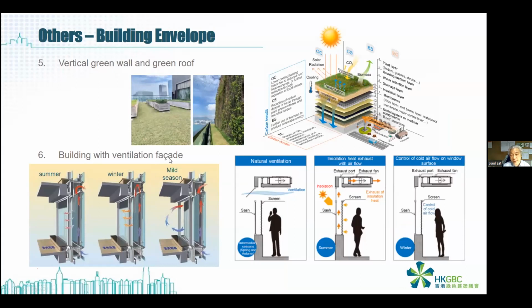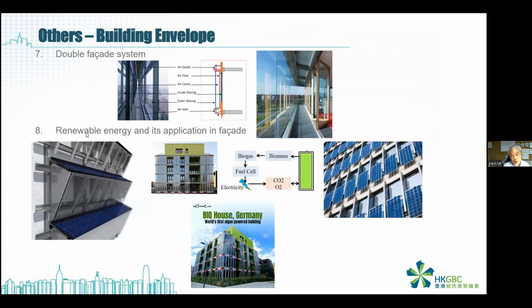We can use some ventilated facade so that in summer, the air passes through the windows and rejects the heat kept enclosed between the facade layers. But in winter, we want to make use of the air within the facade for the space. Some of them are mechanical, and some require a fan to inject air, together with the openings between the building envelopes. And also we can add some renewable energy, something like that. This is some of the design of the building envelope.